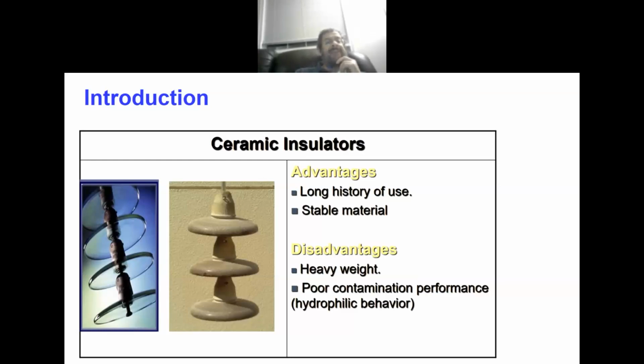The first one is the heavy weight. As I showed in the previous slide, those insulators have to be held by the tower, so they create a mechanical burden on the tower, which has to be strong enough. As we increase the voltage, the length of these insulators increases more and more, meaning more mechanical burden.